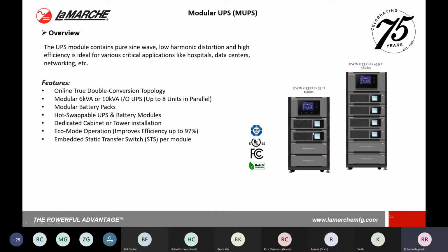So this one now, we start at a 6 kVA module and a 10 kVA module, and we have the capability of paralleling up to 8 of these units together. So that's where you get your total capacity of up to 80 kVA. These again do have a similar style battery pack like the compact UPS. So you have your power modules noted here with a little display and your battery packs right underneath it.